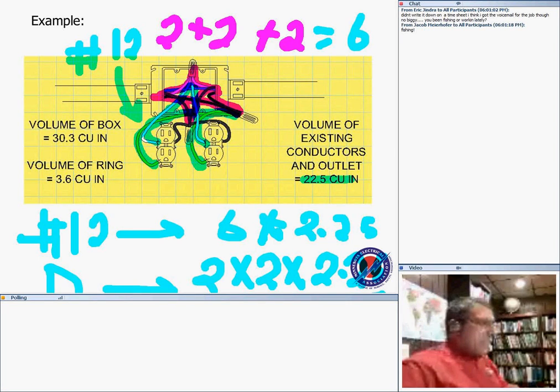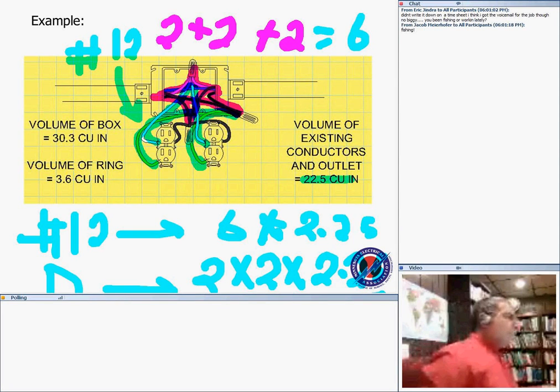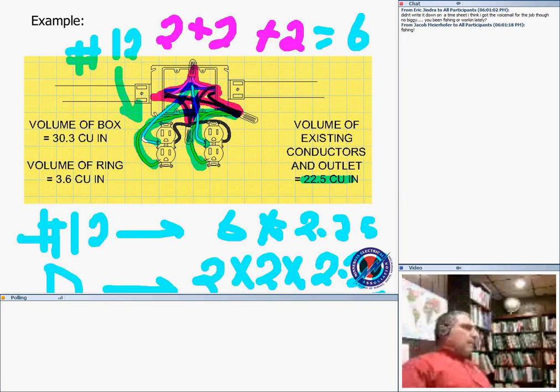Let me remind myself, guys, the devices always count as 2 based on the conductor landing on them. Any pigtails count as 0. Why do they count as 0? Devices count as 2 based on the conductor landing on them. Any questions, guys, about this? Straightforward. A number of conductors terminate. Any conductor that originates outside the box and terminates inside the box counts as 1. But it has to start outside the box.